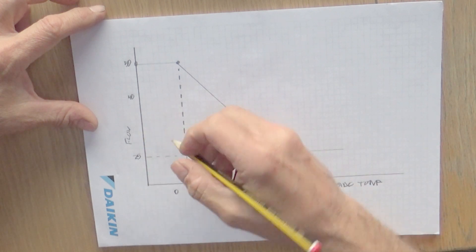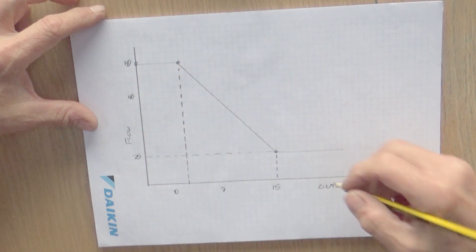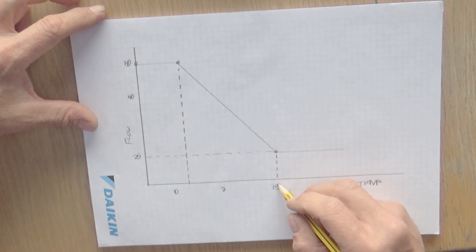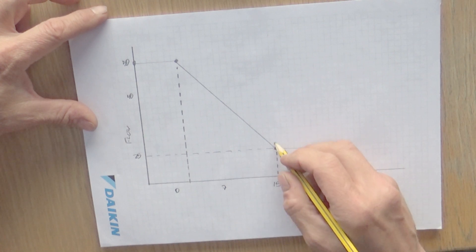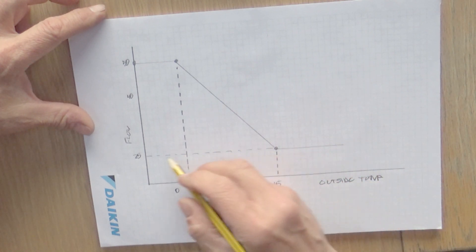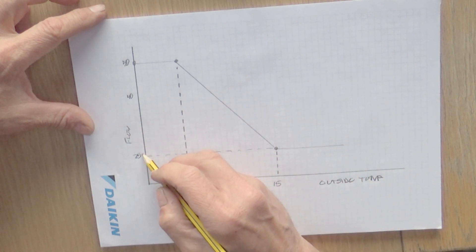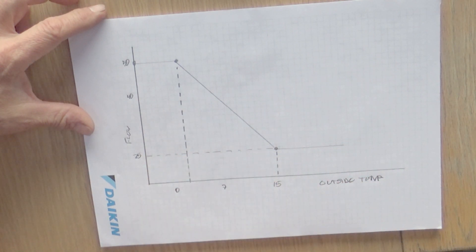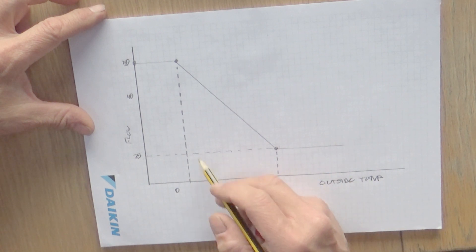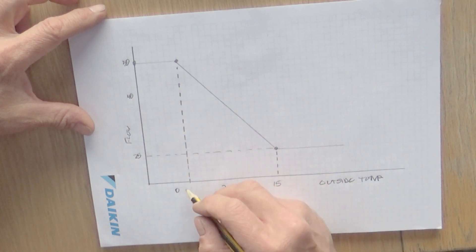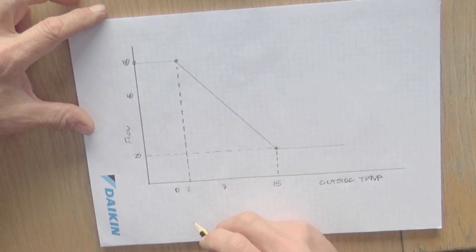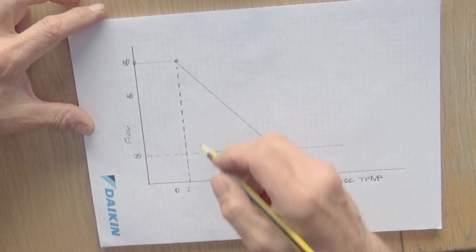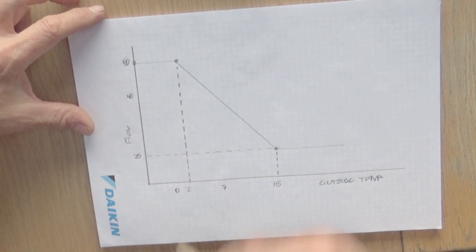For example, with a boiler, you could set a curve up so that when it's 15 degrees outside, a gas boiler could run at 25 degrees flow. And at the other end of the scale, when it's around two degrees outside, the boiler could run at 50.